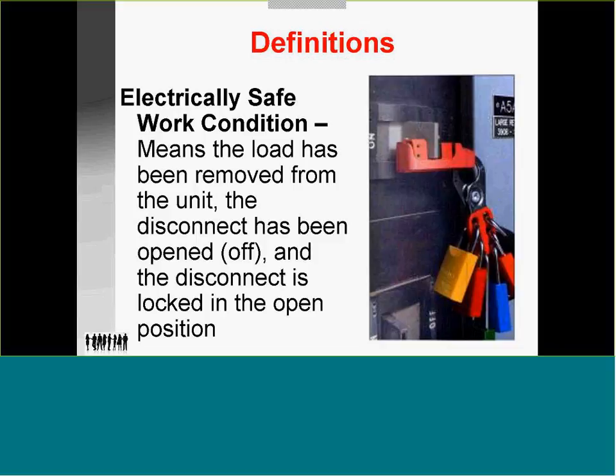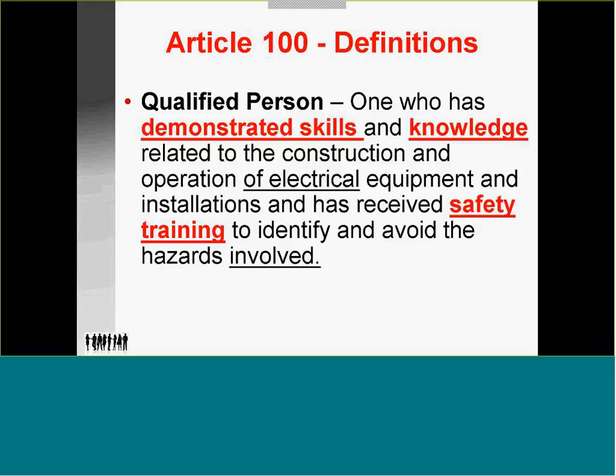Once the unit has been isolated, then disconnect. And that's when you turn it off. The disconnect is locked in the open position. This is critical. If it is not locked, it is not considered electrically safe. And paddle switches do have devices that can be put on them. Everyone out there does have a device that can be used to lock it out. Now, a qualified electrical person is someone who has demonstrated skills and knowledge related to the construction and operation of electrical equipment and installations and has received safety training, the key factor, to identify and avoid hazards involved.